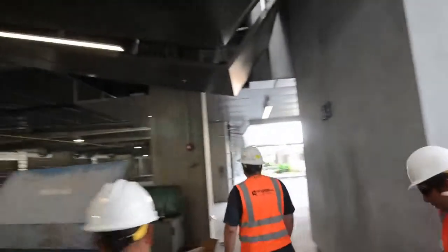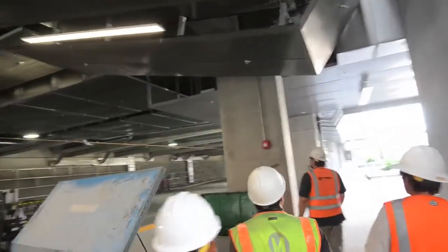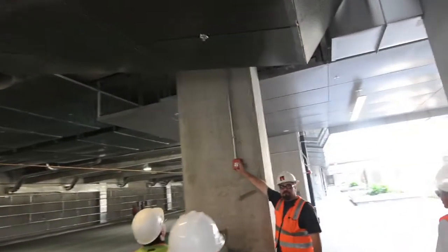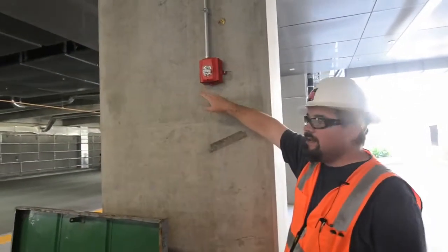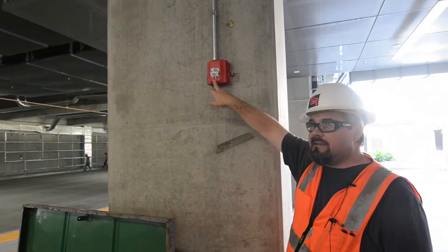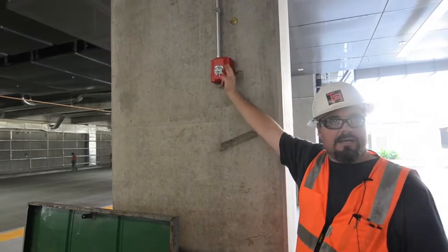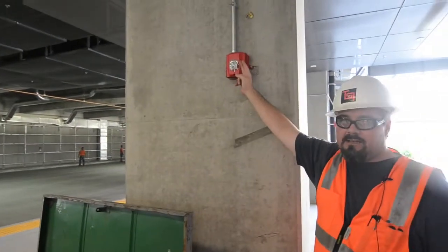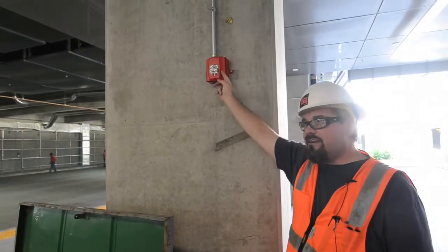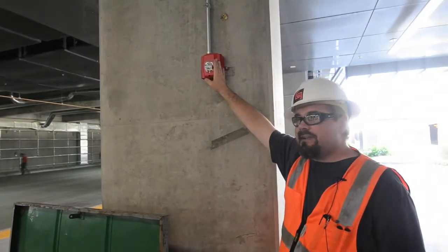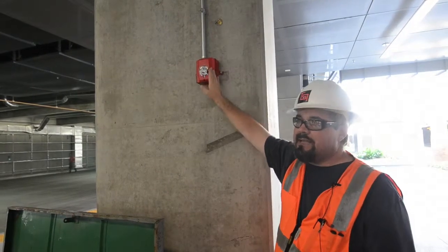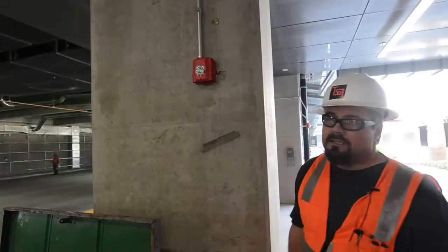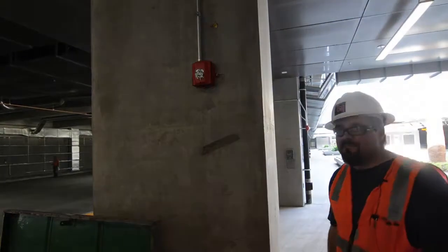But let's see here. Here's a regular strobe right here. Now these are outside weatherproof plain labeled strobes, and these are high candelas because they're sort of outside. So these should be all 185 candela, and they don't have any lettering because we don't want to confuse anyone when we have a gas alarm. Typically you'll see fire on it, so when they go off, we don't want the people to freak out that it's a fire, but it might not be a fire, it might be just the gas is building up. So that's why they're all plain, but they're all waterproof, and I wouldn't say they're spray proof, but they're...